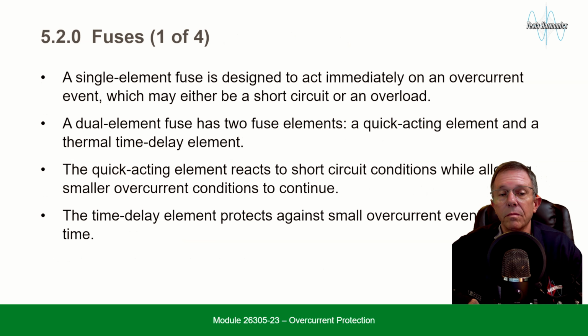Fuses. A single element fuse is designed to act immediately on an overcurrent event, which may either be a short circuit or an overload. A dual element fuse has two fuse elements, a quick acting element and a thermal time delay element. The quick acting element reacts to short circuit conditions while allowing smaller overcurrent conditions to continue. The time delay element protects against small overcurrent events over time.